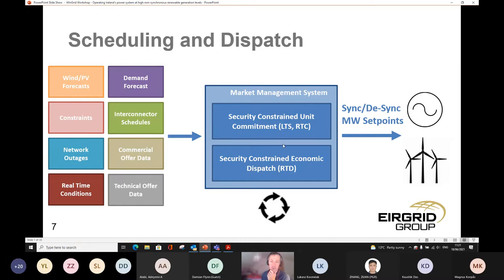More granular then, and looking shorter term, is the economic dispatch. So knowing what's on the system at the minute and the cost of the units on the system, what dispatch signals in terms of changes to megawatt set points on the generators we need to make in order to keep the system secure, but also to keep it running economically. This is a continuous process, which I'll illustrate in another slide, where we're running hundreds of iterations every day to ensure we're keeping the system secure and economic.